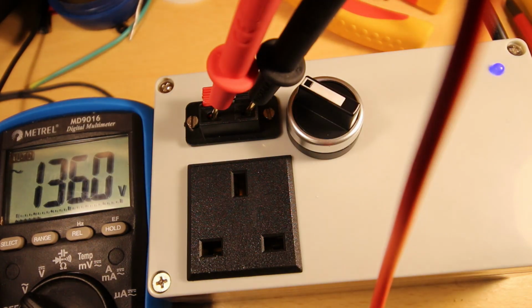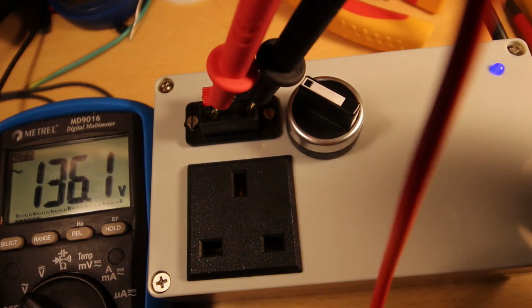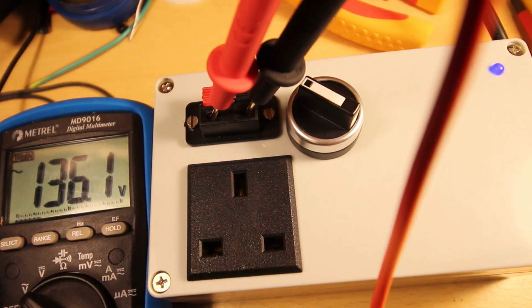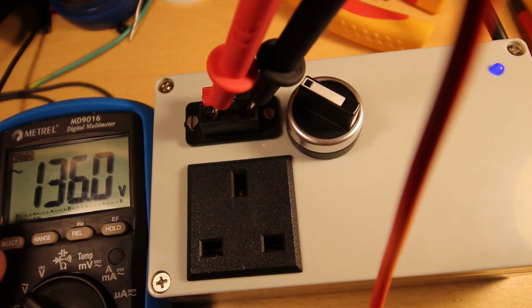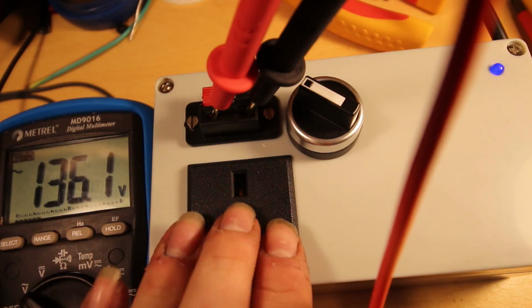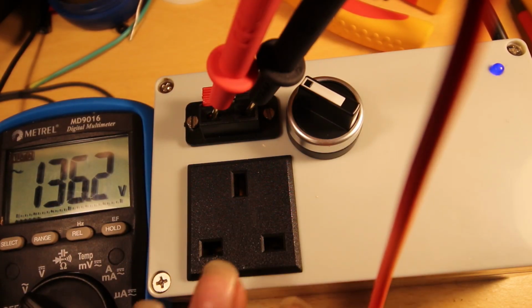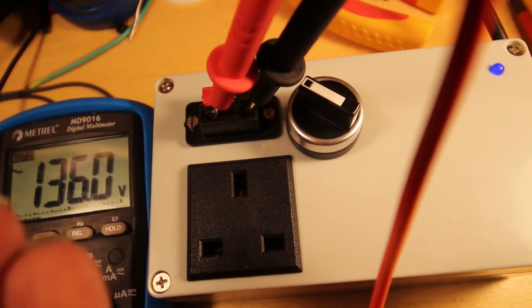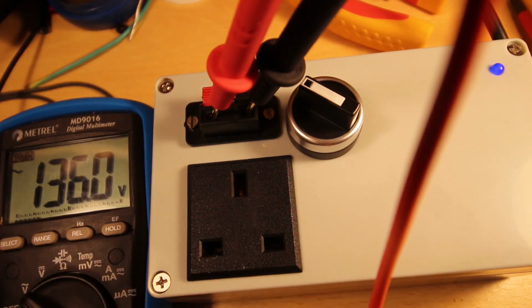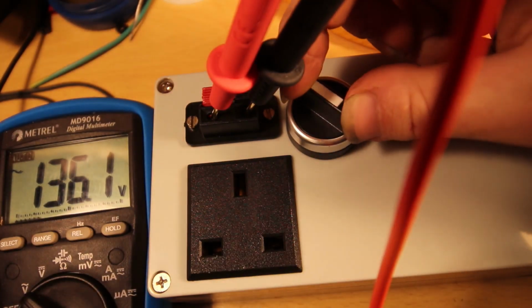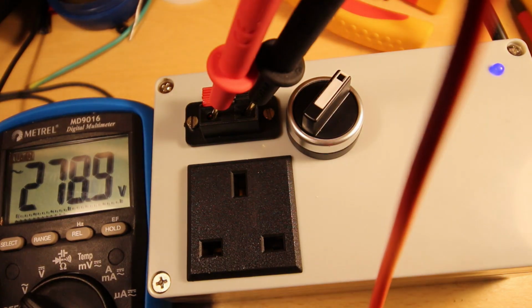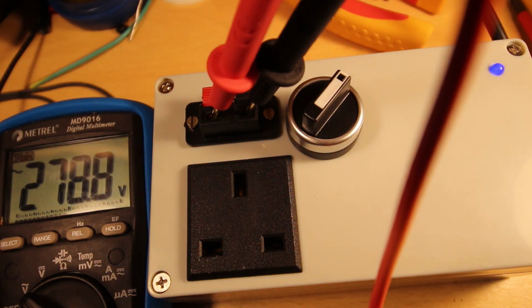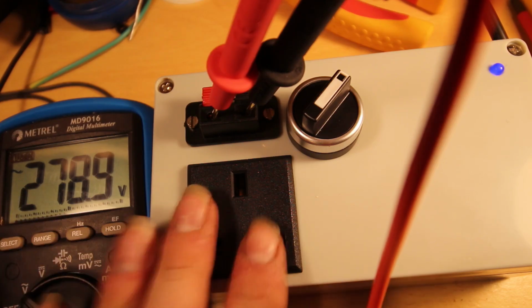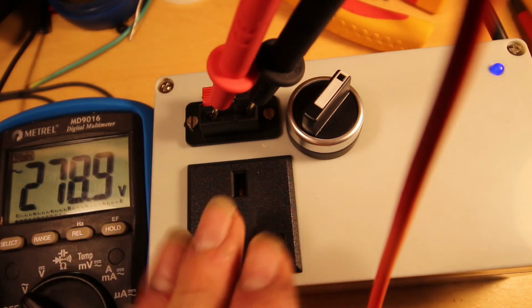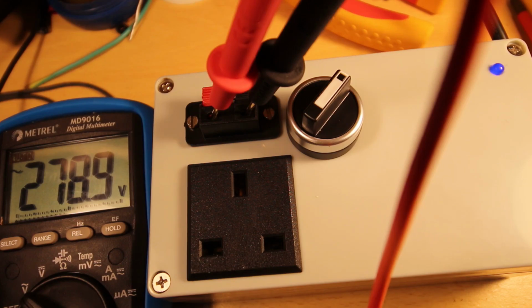We have 136 volts there, and that blue indicator has come on as well, which is good. The reason the voltage is quite high is because there's no load on the transformer at the moment, so the voltage drifts up - as soon as you draw current from it, it will drop down. If I turn this round, we have 278 volts, again quite high because there's no load. As soon as this is loaded, that will drop down.